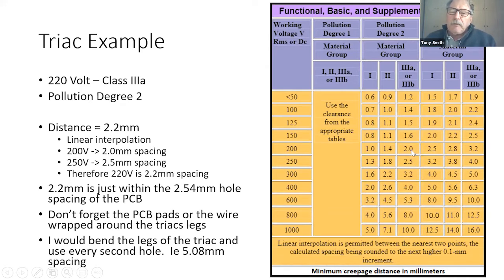We come down and it's around about 2 mil to 2.5 millimeters spacing. You can do linear interpolation, so 220 volts would be say 2.2 millimeters. But it gives you a sense that it's far more than the 1 millimeter for just the air gap. Now 2.2 mil is just about very close to the 0.1 inch, 2.54 mil hole spacing in a PCB.